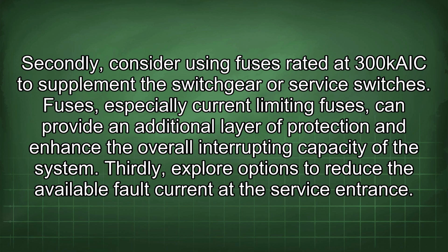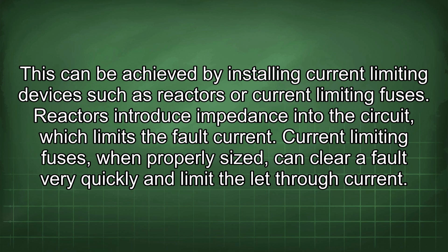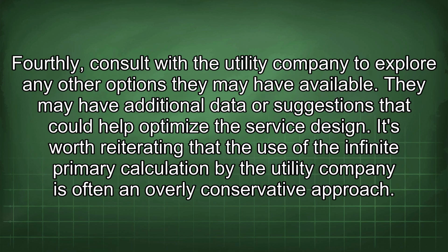Thirdly, explore options to reduce the available fault current at the service entrance. This can be achieved by installing current-limiting devices such as reactors or current-limiting fuses. Reactors introduce impedance into the circuit, which limits the fault current. Current-limiting fuses, when properly sized, can clear a fault very quickly and limit the let-through current. Fourthly, consult with the utility company to explore any other options they may have available. They may have additional data or suggestions that could help optimize the service design.